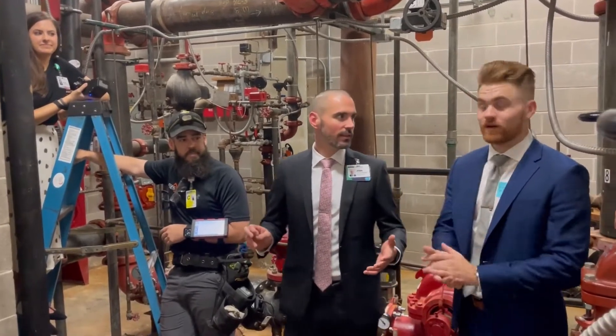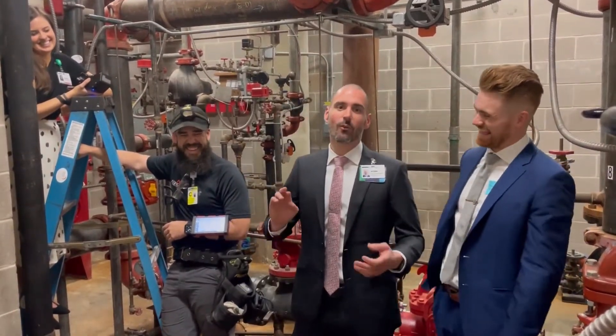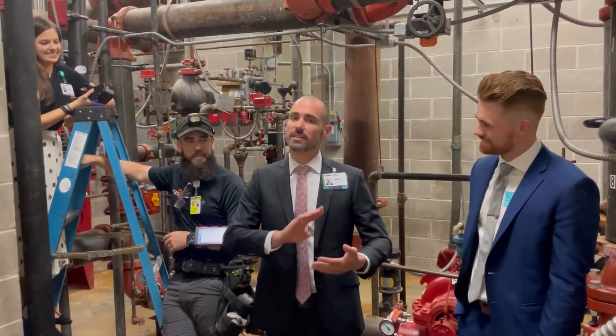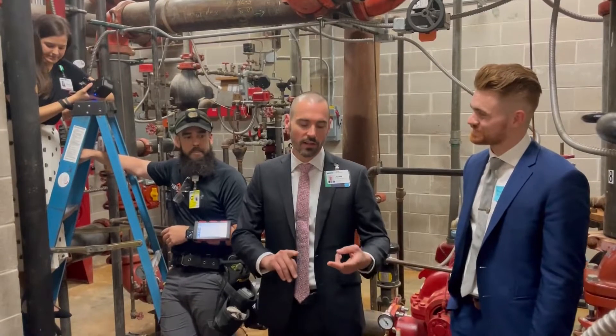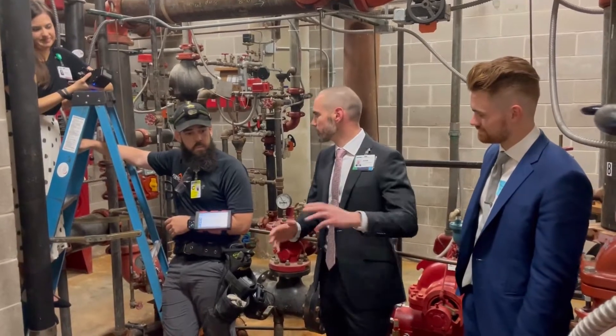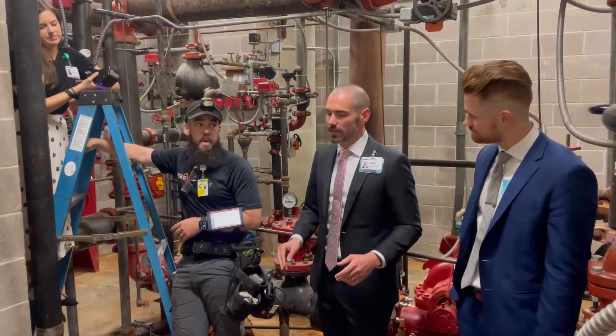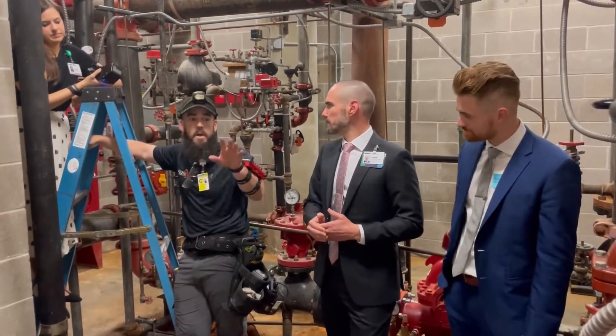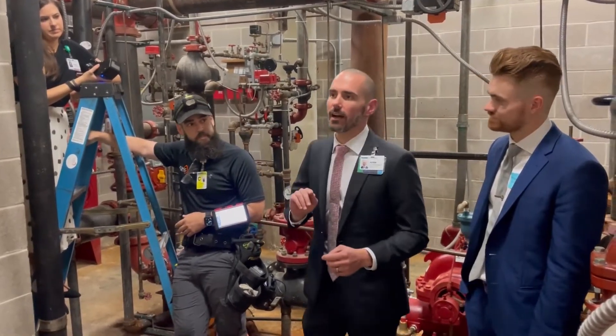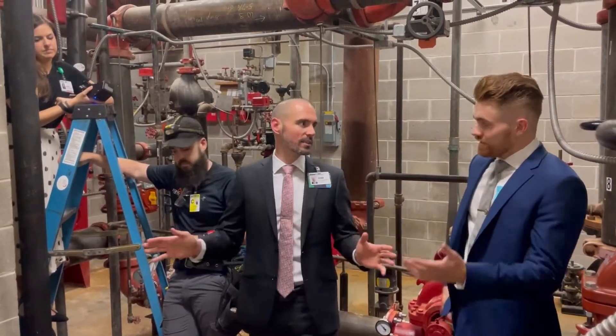We chose this method because it is non-invasive. You have to test 50% of your sprinkler systems every five years anyway, so: non-invasive, less cost, faster. The destructive method takes anywhere between four to six hours — draining it down, filling it back up. This takes about 30 minutes per system.